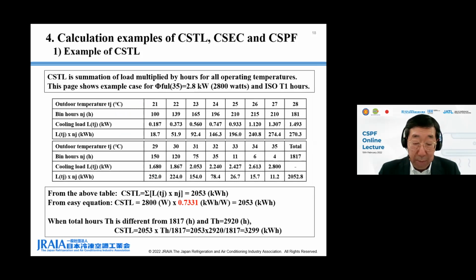CSTL is the sum of load multiplied by hours for all operating temperatures. This page shows a calculation example for 35 degrees C full capacity 2.8 kilowatt and ISO T1 bin hours. In this table, the first line shows outdoor temperature TJ. The second line shows ISO T1 bin hours NJ at each TJ. And the total of this line in the lower right end row becomes 1,817 hours, which was shown in the figures of ISO T1 hours in the previous page. The third line shows cooling load at each TJ, which can be calculated as shown in the example of ISO T1 load in the previous page.